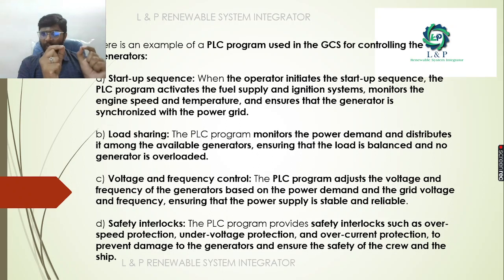startup sequence. During that, the operator initiates the startup. So the PLC activates the fuel supply and ignition system. It monitors the engine speed and the temperature and ensures that the generator is synchronized with the power grid. Second is the load sharing. The PLC program is made in such a way that it monitors the power demand and redistributes it among the available generators, ensuring that the load is balanced and no generator is overloaded.